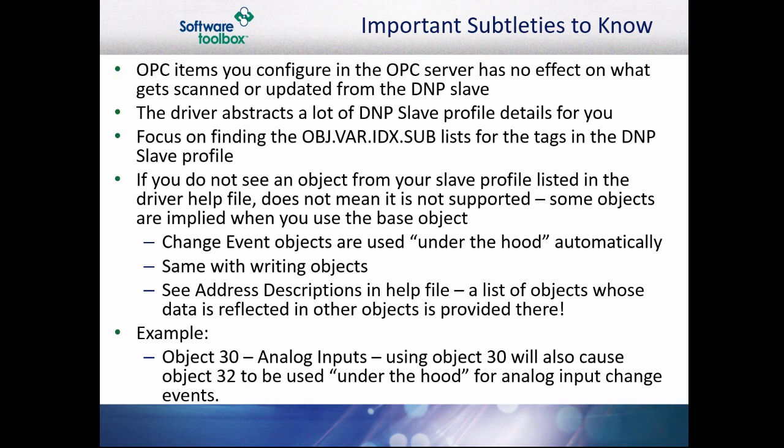The important part is to focus on finding the addressing list in your slave profile. This process could take some time. If you understand DNP3 addressing and your DNP3 slave device vendor has provided a clear and concise document, this process will not be too difficult. If you don't see an object number from your slave profile list and the address is supported by the server, this does not mean it isn't supported. Some objects are reflected or addressed under the hood using a base object. There is great detail in the help file about these objects. For example, if you wish to read from object 32, you would address that by using the correct variation for object 30 to cause object 32 to be used.